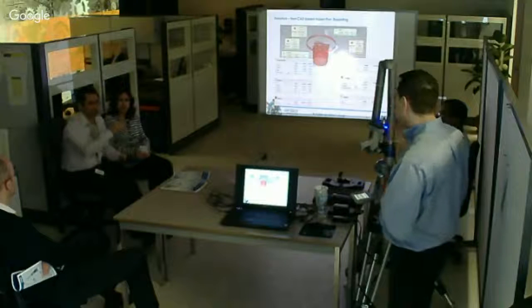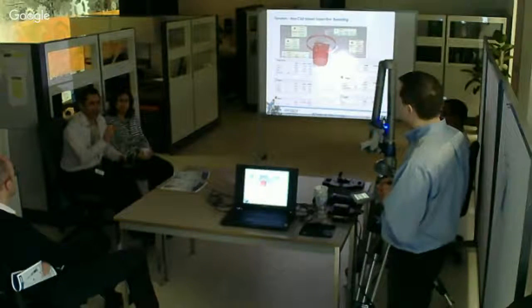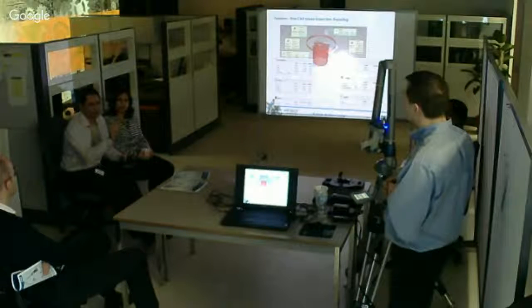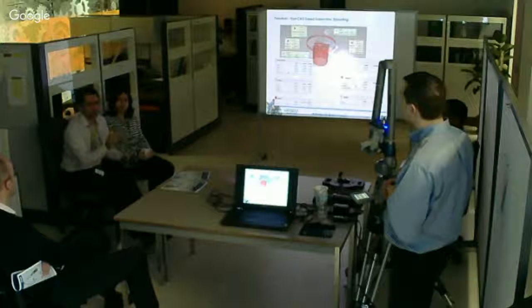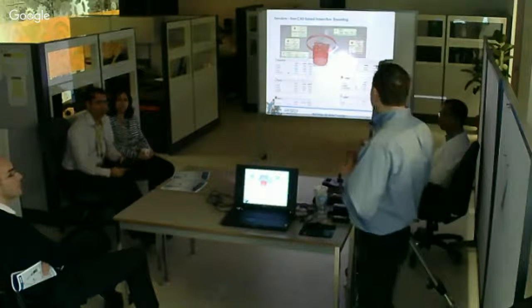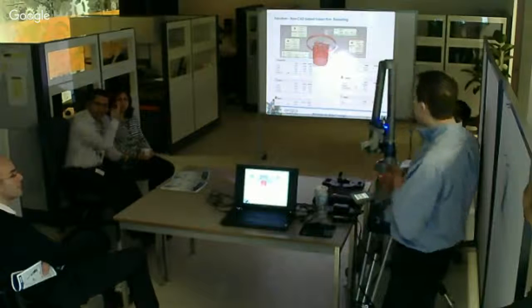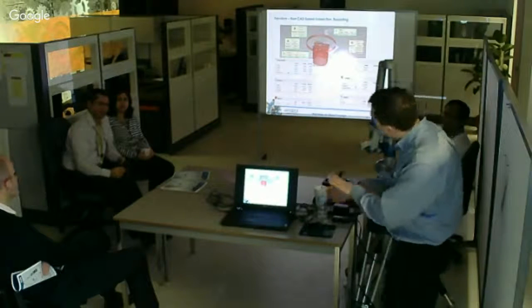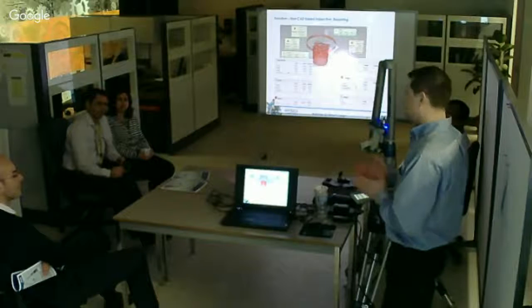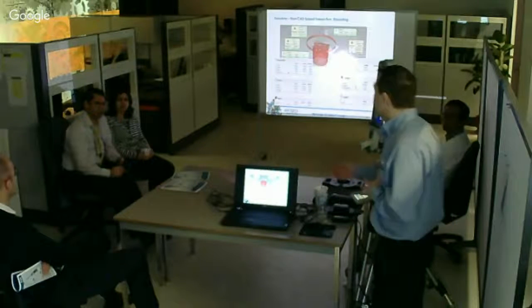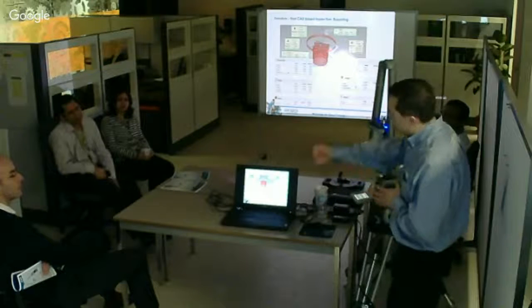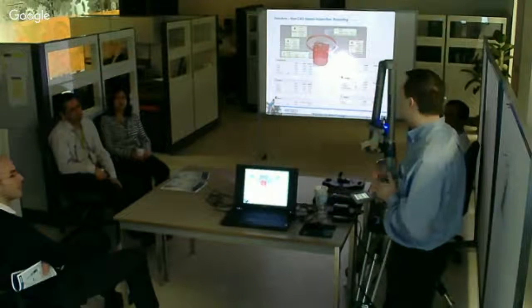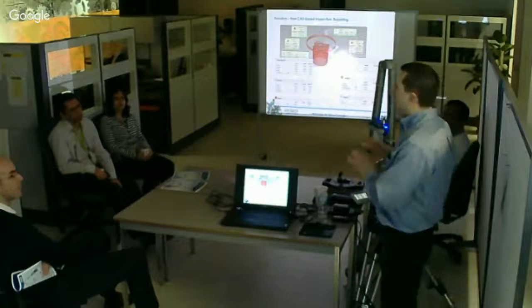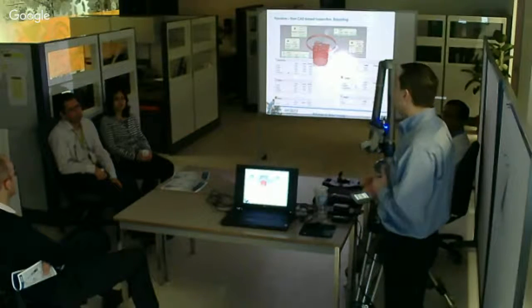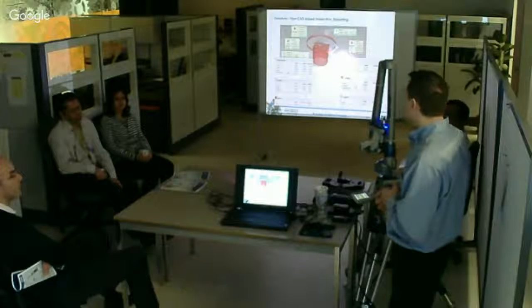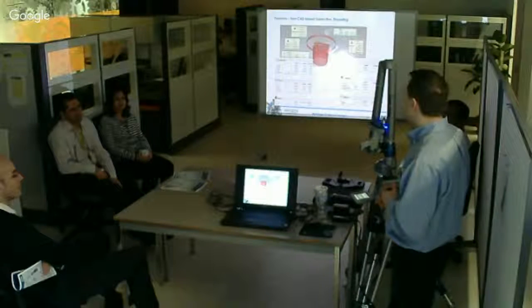There are inaccessible areas where you need to do a 3D analysis to make sure of consistency. Yeah, I mean there are limitations of the probe, excuse me, but we do have probes that are even hooked or bent so you can go around corners. It just depends how big the engine is and how much room you have to get in. We do have probes that hook in at 45 or 90 degrees, and all that is calibrated by you before you do the job, so you can make sure it's within your specifications. We have different probe tips that should hopefully be enough to get your measurements for that.